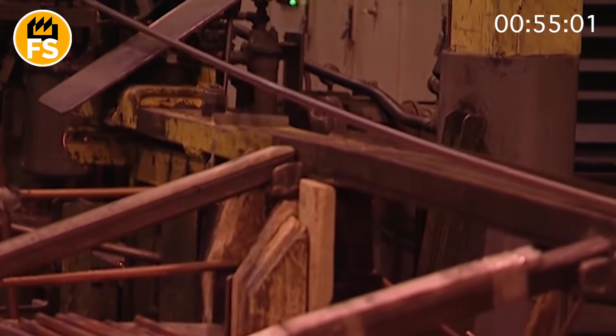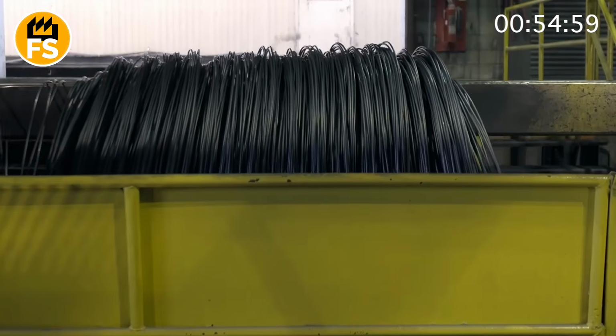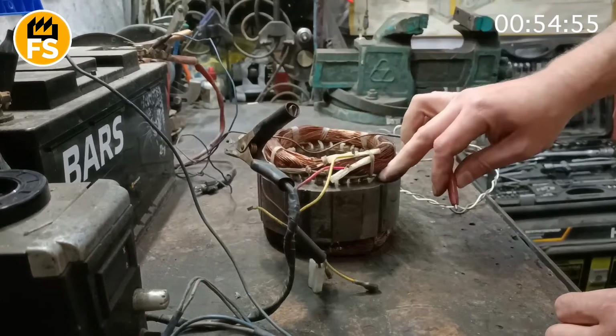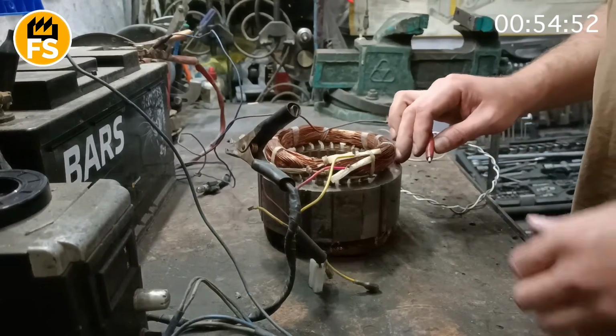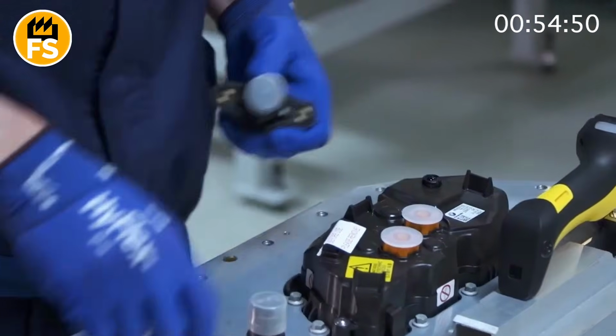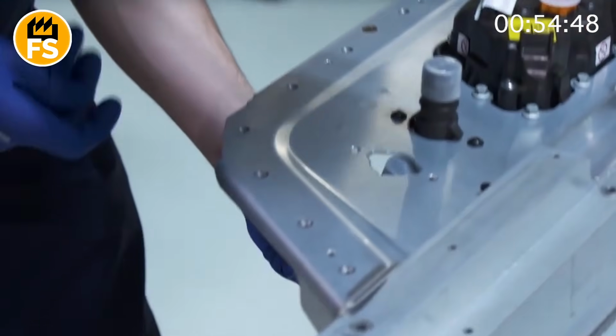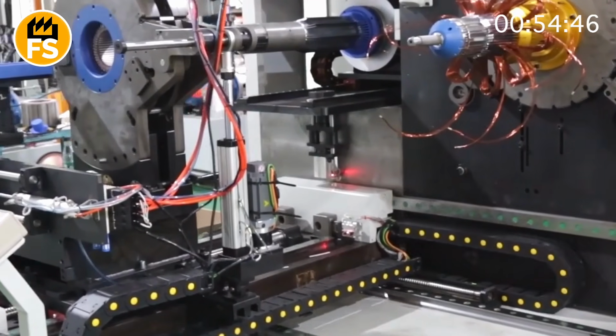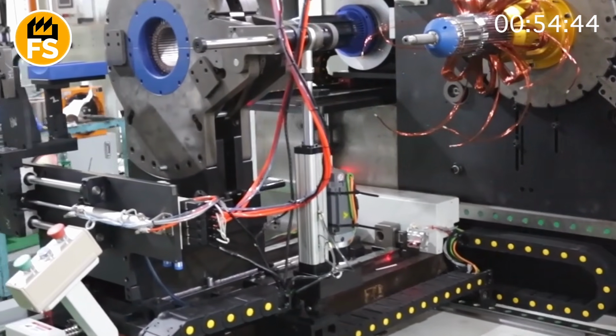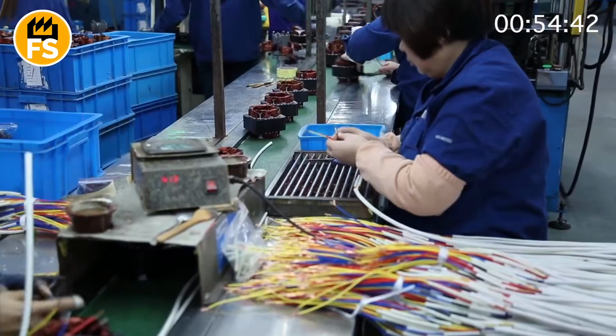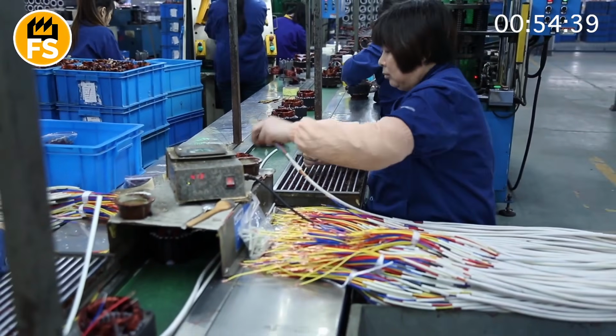For powerful or non-standard motors, winding is done by hand. A worker inserts the wire in a loop, pulls it through with a tool, presses it to the bottom of the slot, secures it, and tightens it. The work is similar to weaving, but with shiny copper and immense responsibility. Each coil, and there are dozens of them, must be identical, symmetrical, and correctly oriented.